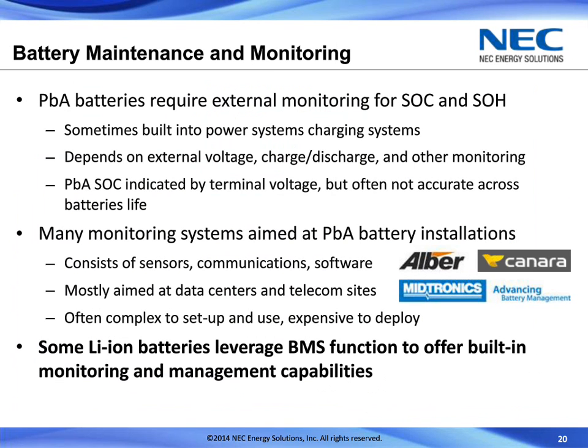The other factor that comes in is, how do we maintain and monitor the health of the batteries in different environments, particularly when talking about industrial environments where batteries may not be easily accessible. Lead-acid batteries often require some sort of external monitoring capability to look at what the state of charge might be and what the state of health of the battery is. Sometimes this is built into the power management systems and charging systems. They actually count how much energy comes in and out of the battery. Sometimes we look at the external voltage of the battery to get some kind of guess on what the state of charge actually is. But often that's not always that accurate.